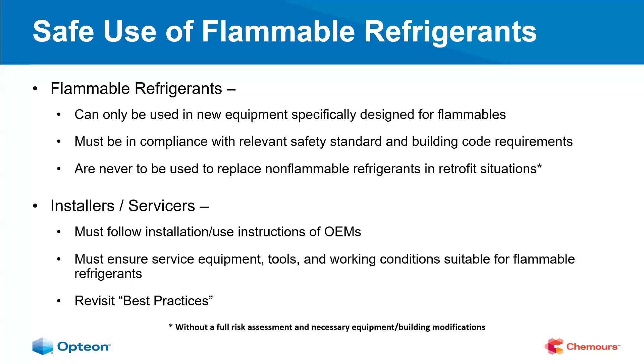It's critical for installers and servicers to follow the installation and use instructions provided by equipment manufacturers — OEM manuals are an excellent source of information on the changes required to equipment designs and installations. Service technicians also need to make sure their equipment is suitable for A2L systems. Many of the tools used today with A1 refrigerants will work with A2Ls, however recovery machines, vacuum pumps, and leak detectors are equipment you specifically want to check to ensure they're rated for A2Ls. Tool manufacturers have had A2L-rated equipment available for a while, so check with the tool manufacturer to be sure.